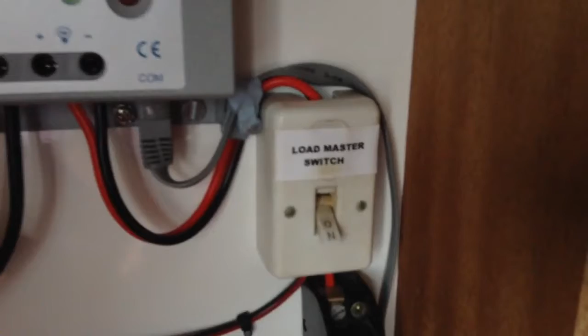This is the charge controller. On the DC output side, I have a switch turning off the output, then I go to a circuit breaker, basically just an automatic overload switch—a 5 amp breaker in this case. I did say the charge controller can handle up to 20 amps on the output, so this 5 amp breaker goes to my DC fuse box, a simple automotive fuse box, and then I wire out to my load devices.